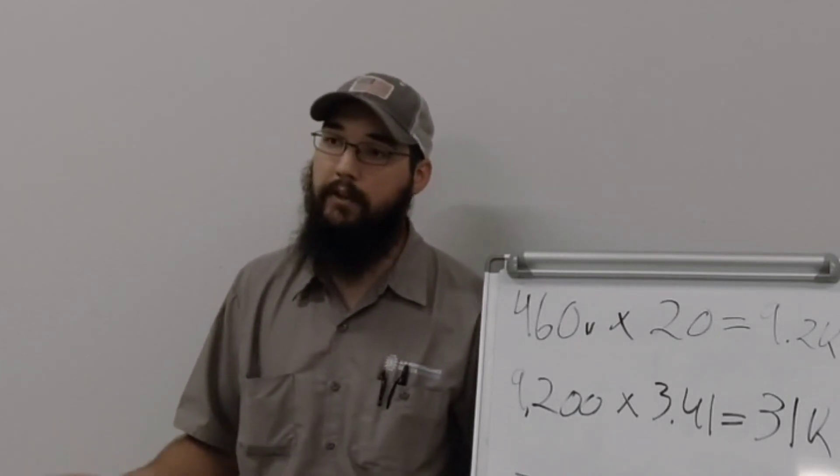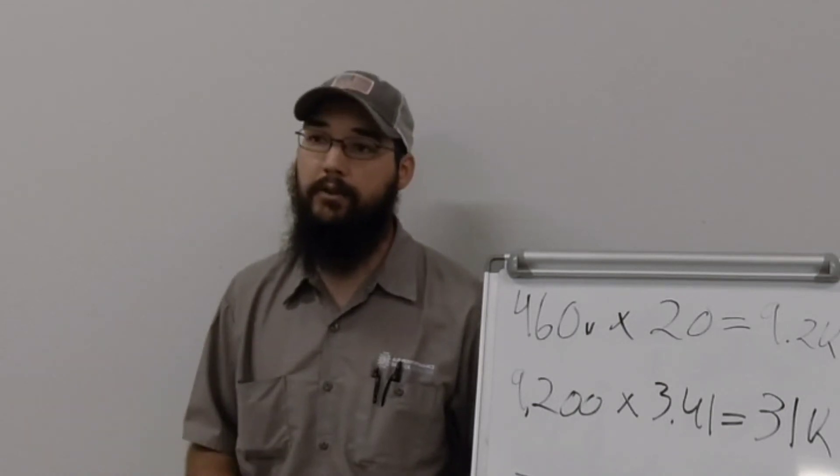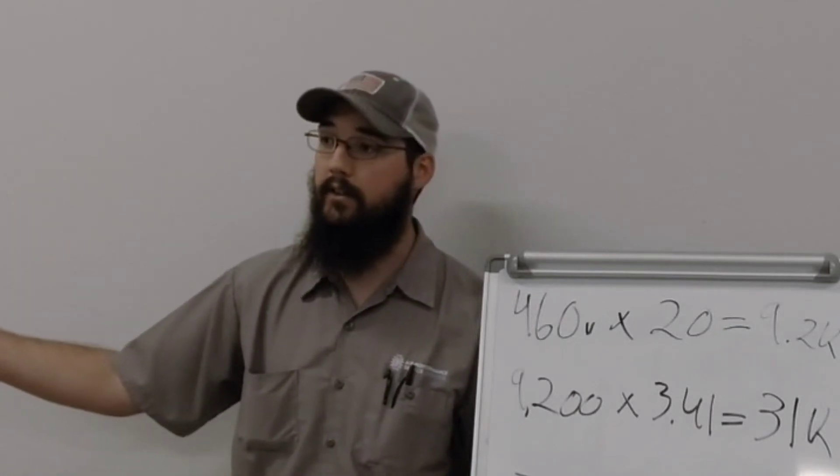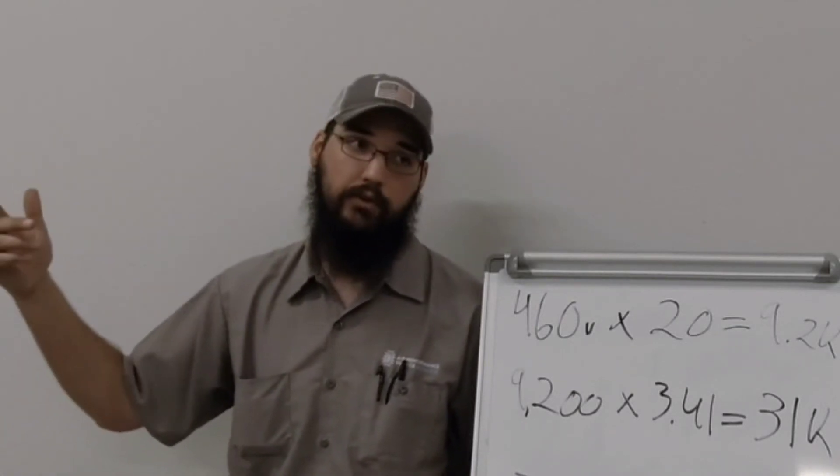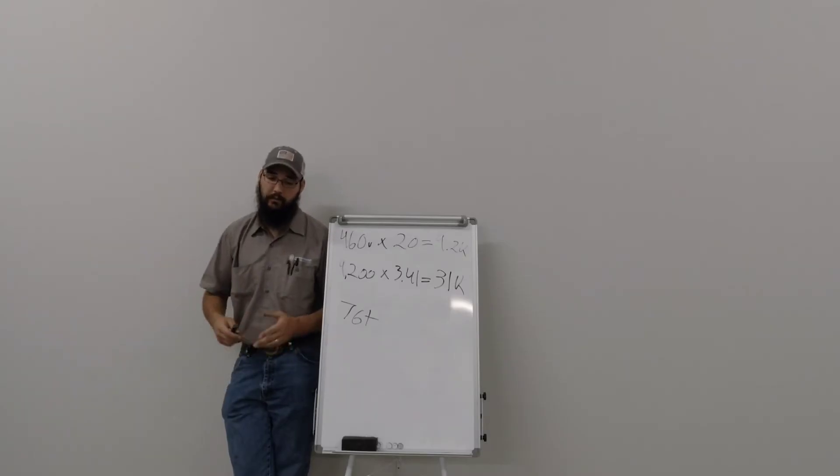If you've got a, if you're moving that fan at 100 percent, something's probably wrong. That, or you've got a really high load. I mean, you'll see that if the floor is hot after it's been shut down for too long, you might see that, but you should not maintain that. All that ties back into the load of the system.